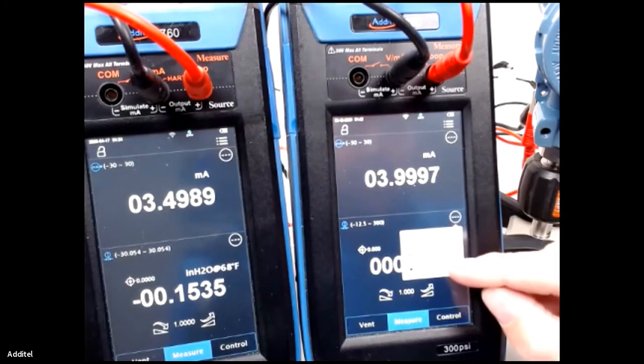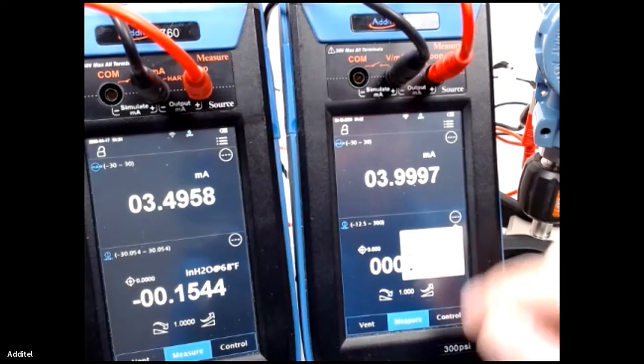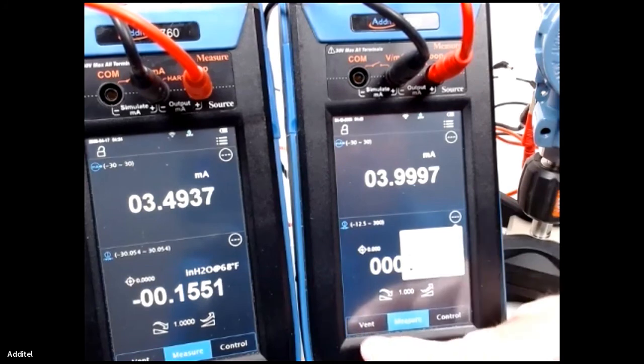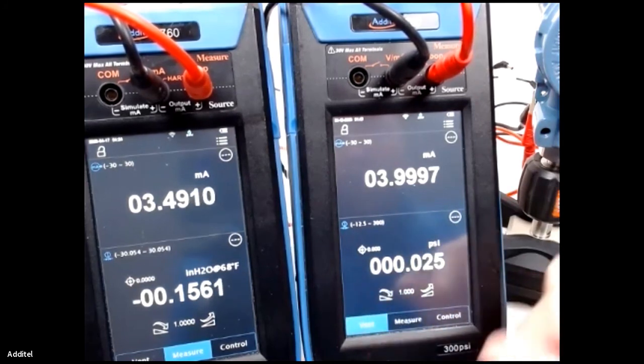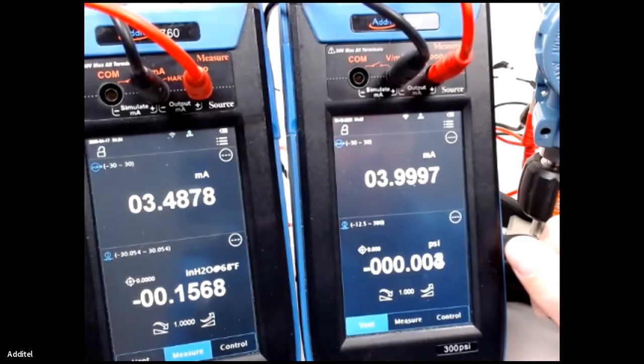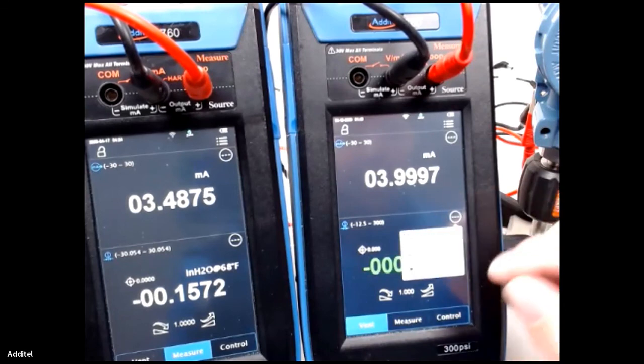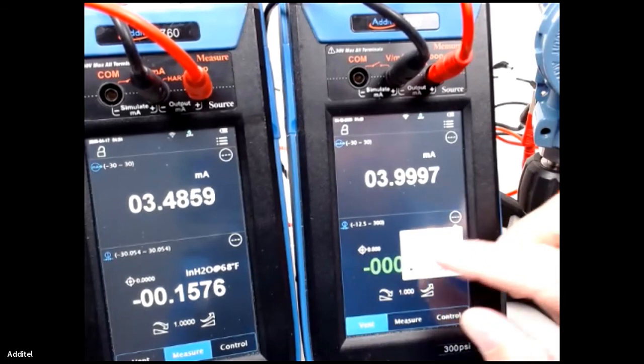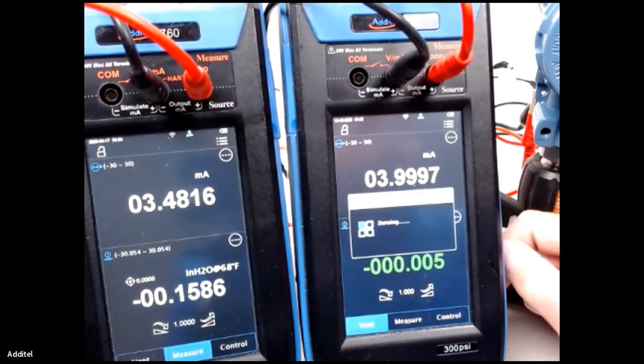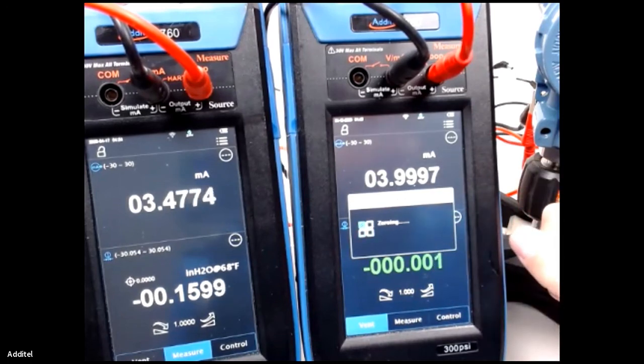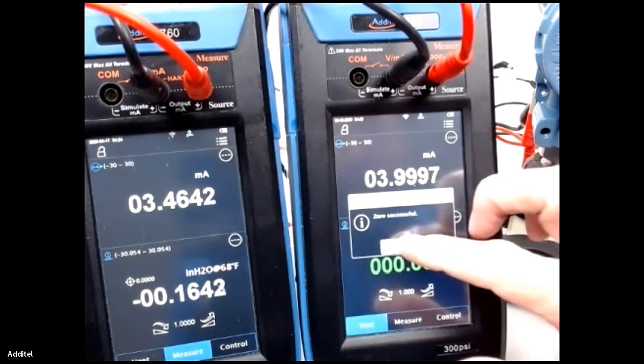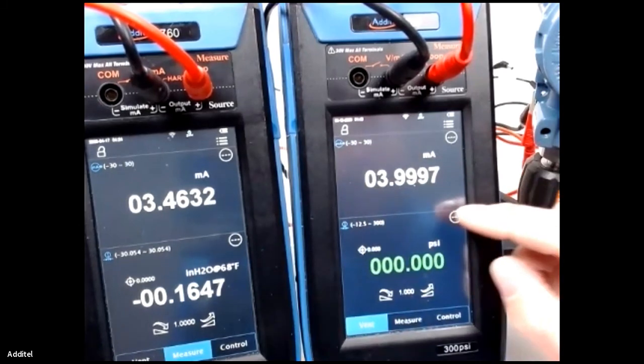So in this menu there's a 0, so we can go ahead and zero our pressure unit. I'm going to vent it first, so we start out on vent. Looks like it's pretty close to 0, but let's go ahead and zero it. You just hit that and it auto zeros, so it pops up on the screen telling us we're zeroing the unit. And then once that gets done, you can see that it's already zeroed now. You just press OK and you're done with that.